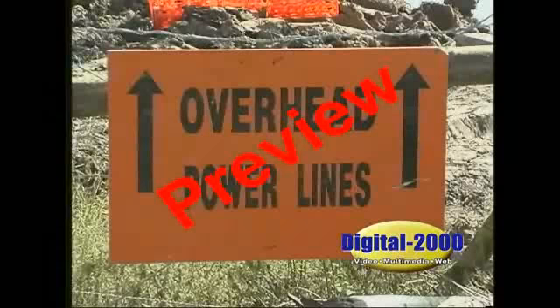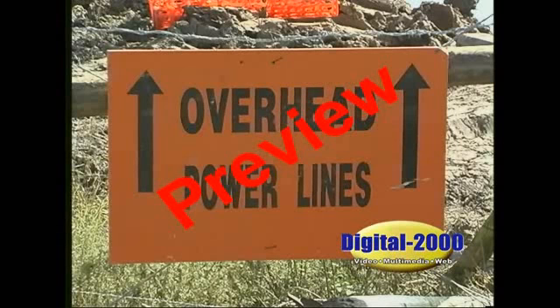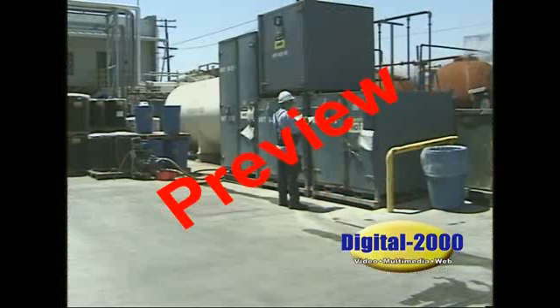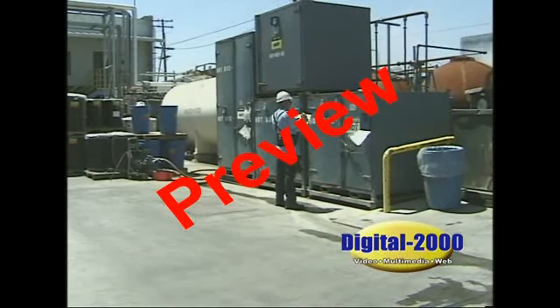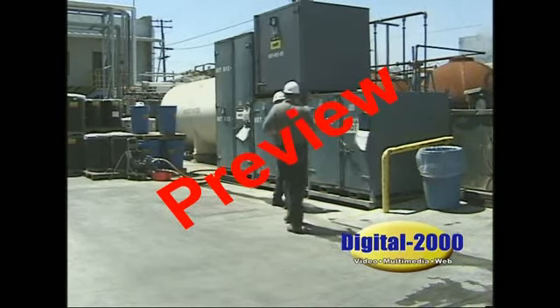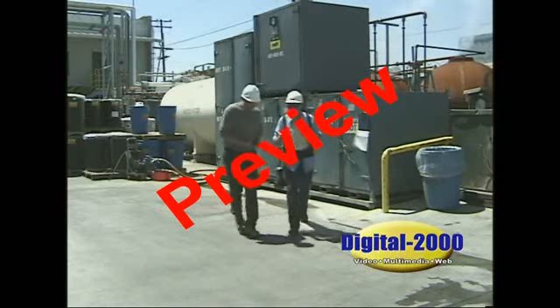In addition to the PPE requirements, the latest update to NFPA 70E provides a requirement for field labeling and a requirement that work on energized electrical equipment have work permits to ensure people performing this work are properly trained and equipped. Arc flash labeling requirements.